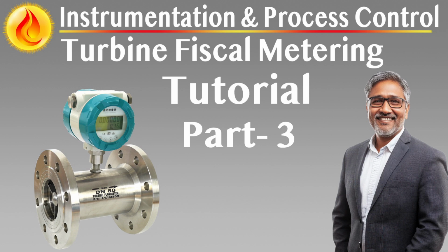K-factor management and meter factor tracking. Each turbine meter must be assigned a unique calibration factor, the K-factor, representing the number of pulses per unit volume. This factor must be established during initial calibration and manually entered or digitally downloaded into the associated stream microcomputer. The microcomputer must also retain the previous K-factor value to support traceability and audit review during meter factor updates. Meter factors must be recalculated during proving operations, and any significant deviation from prior values must trigger an operator prompt and require confirmation before the new factor is committed.